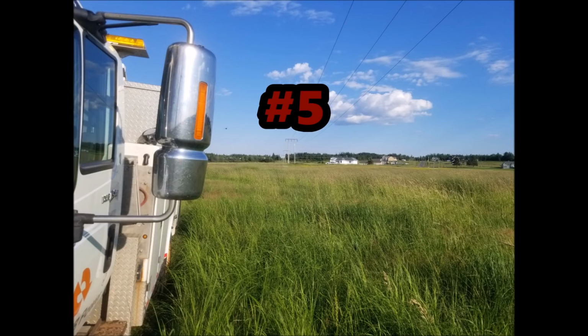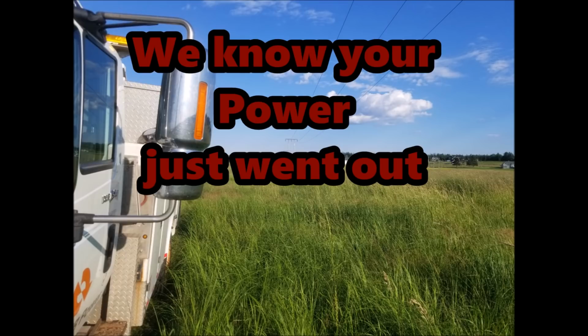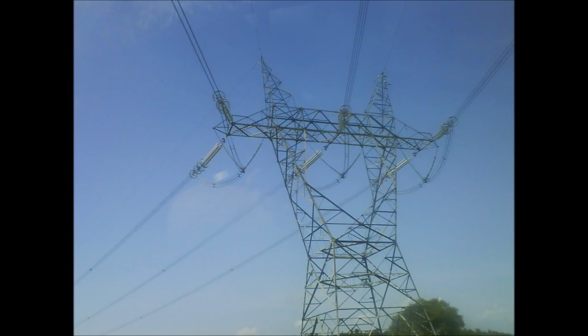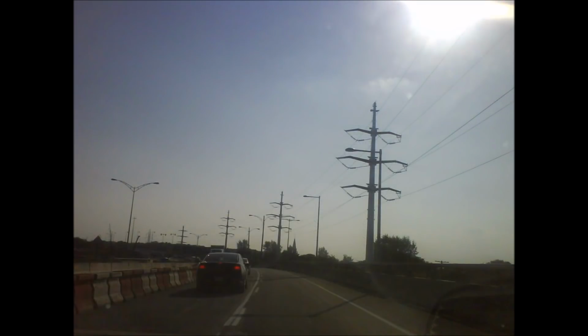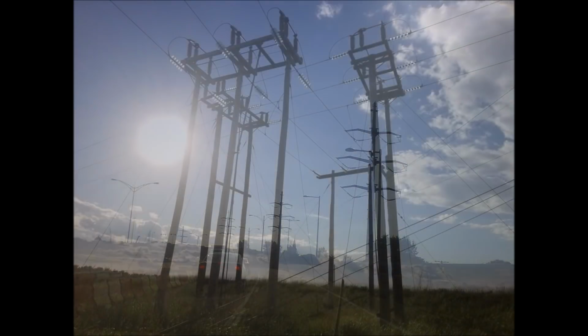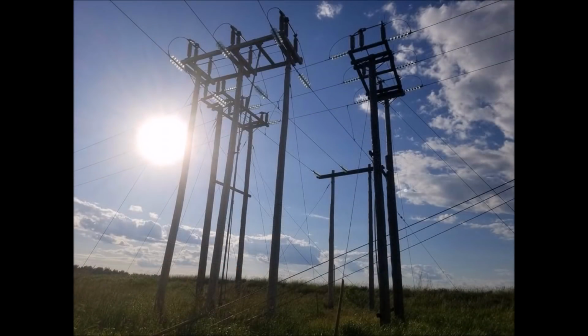Number 5. We know when your power goes out. Now, before I get started on this one, I would like to mention that if one of the transmission lines go out, then yes, our system operators will be notified immediately. Also, the amount of load or current on our transmission lines is monitored very closely. A sudden spike in current may indicate a fault, and a sudden drop may indicate loss of a substation or a feeder.